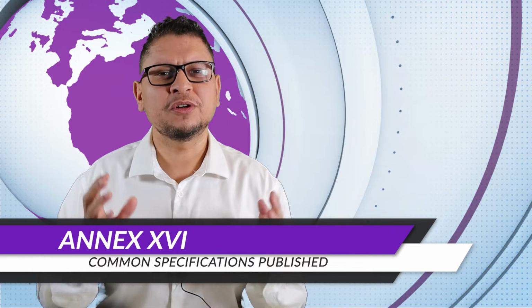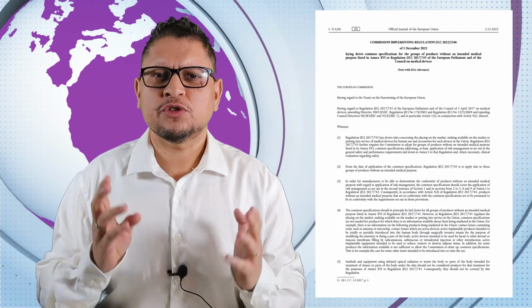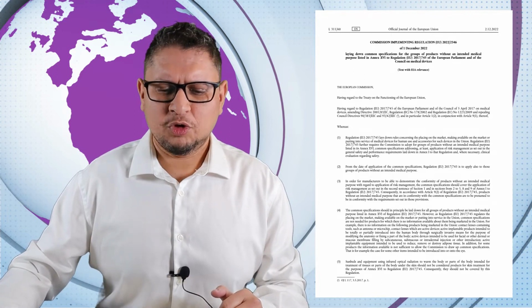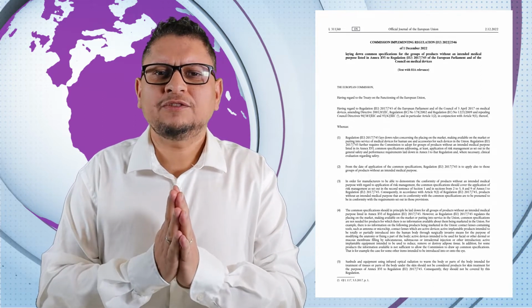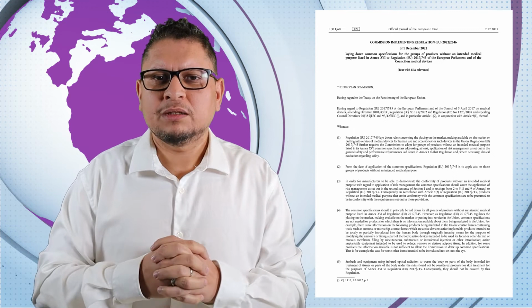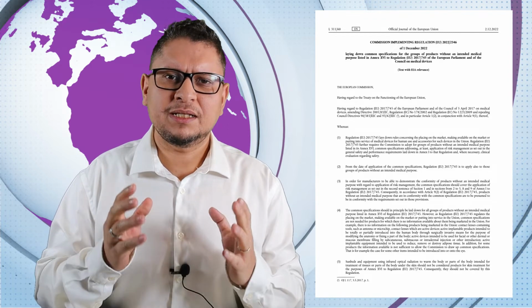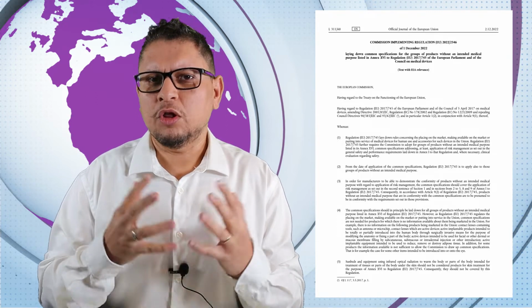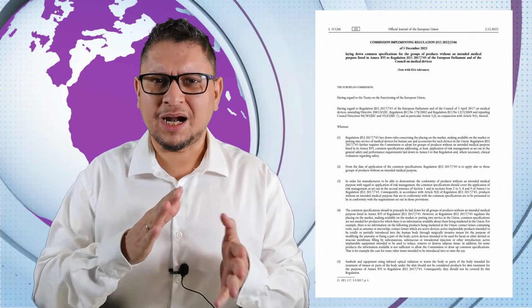Okay, first topic of today, the common specification for Annex 16 products. So finally, it has been voted December 2nd, if I remember, or December 1st or 2nd. So we had the final text. And I wanted just to explain to you a bit more about this new thing. So first, we have the same content as what we had before related to what was in the proposal. Today, what we'll be focusing on is mainly the timelines, because this was a big discussion. On the MDR, it was saying that as soon as it is implemented, it will be a 6-month timeline, etc. Now there are some changes about that.